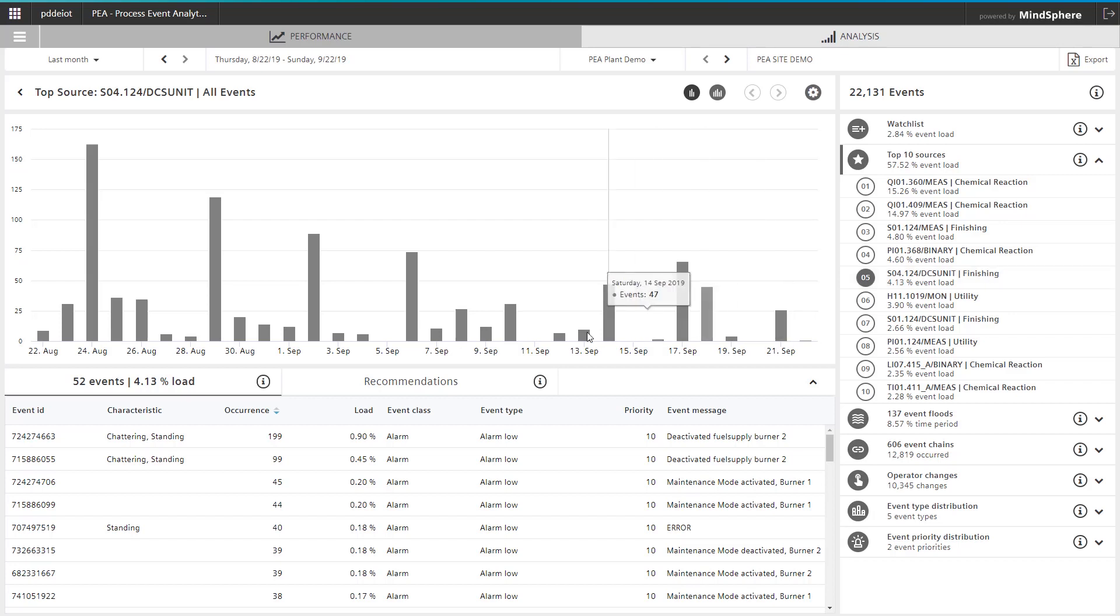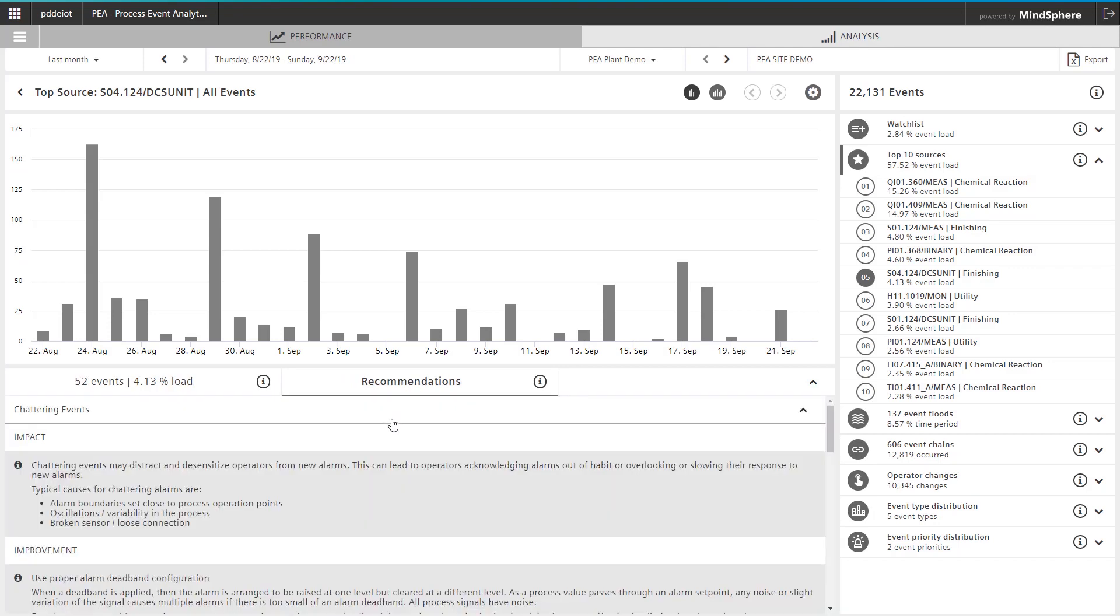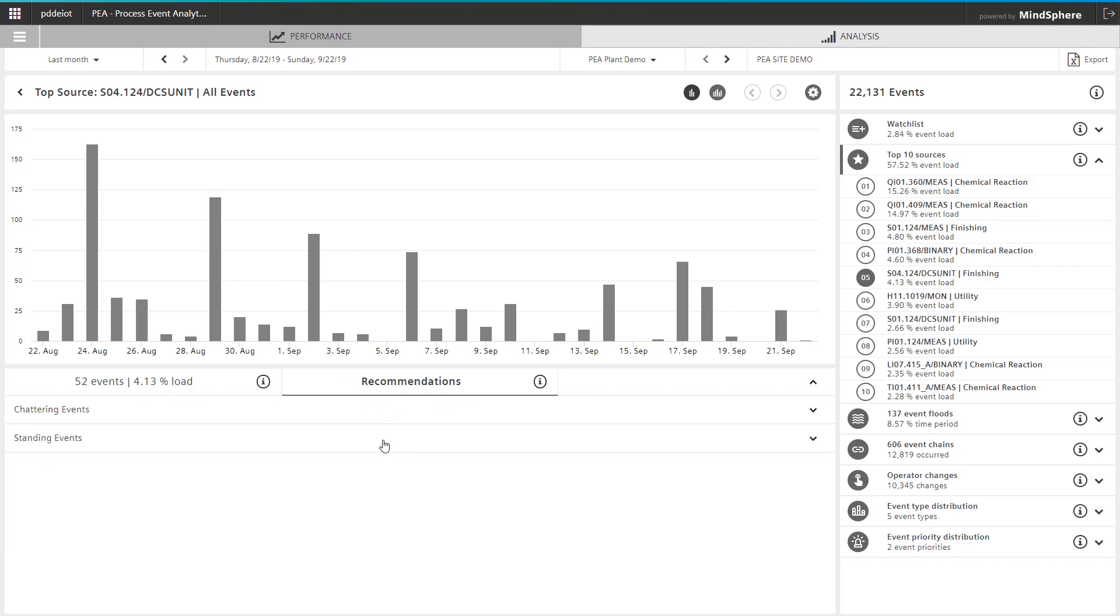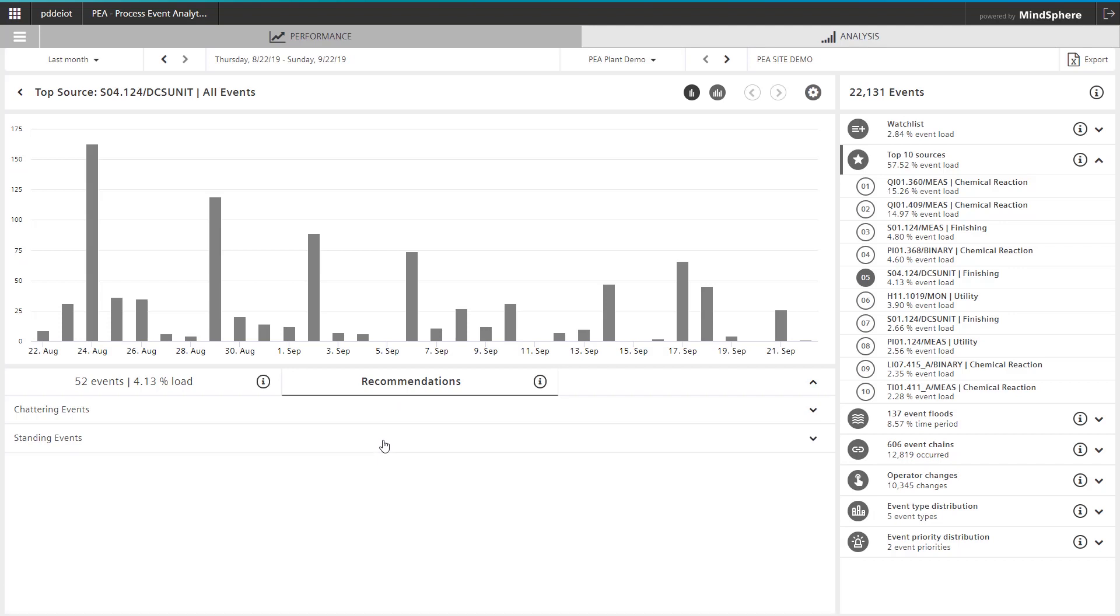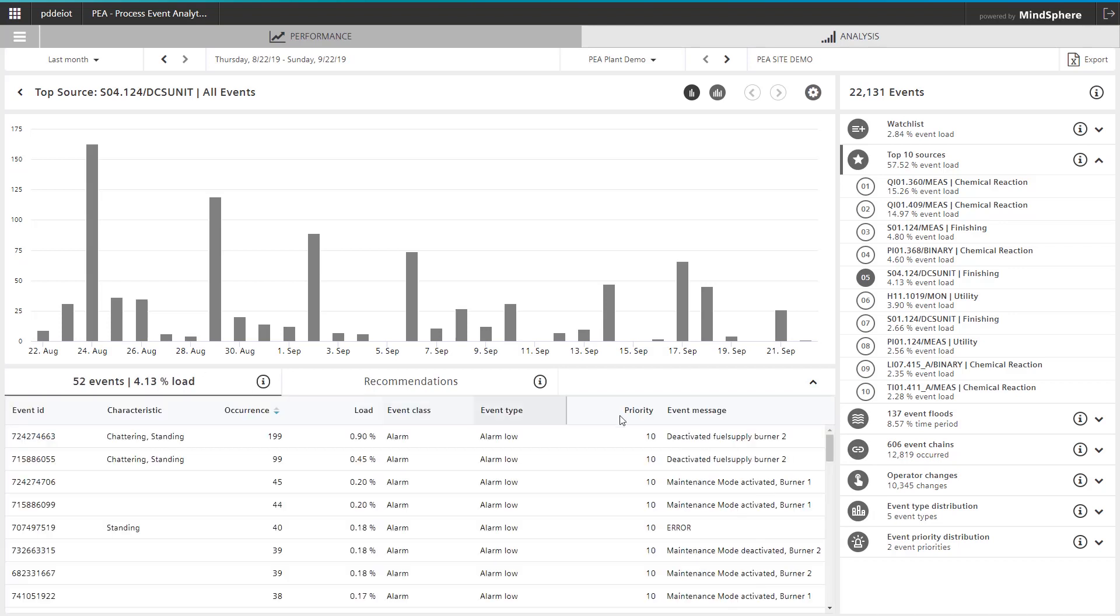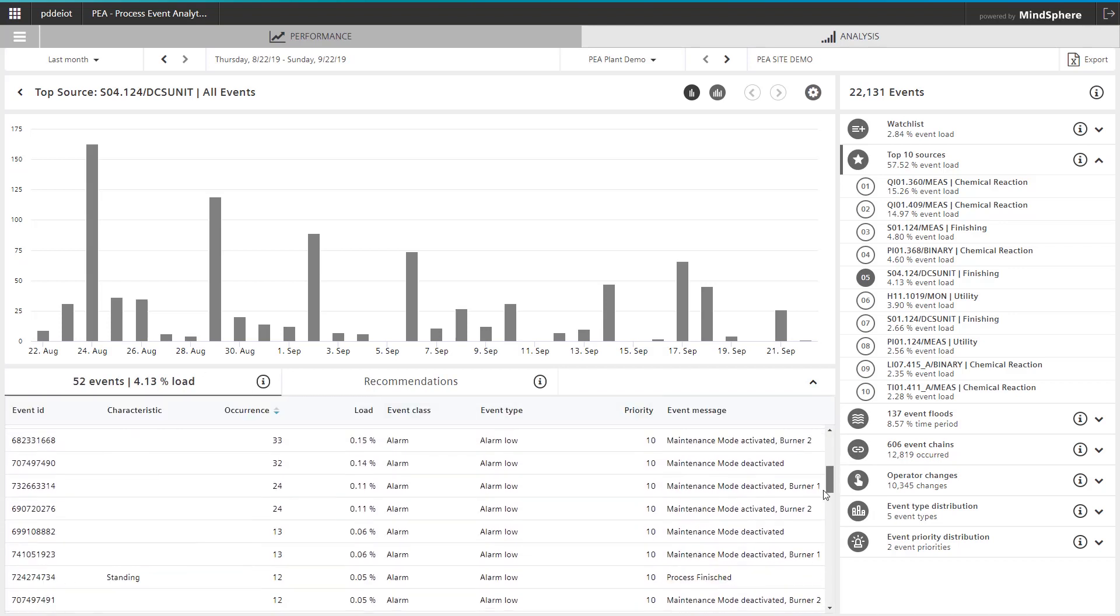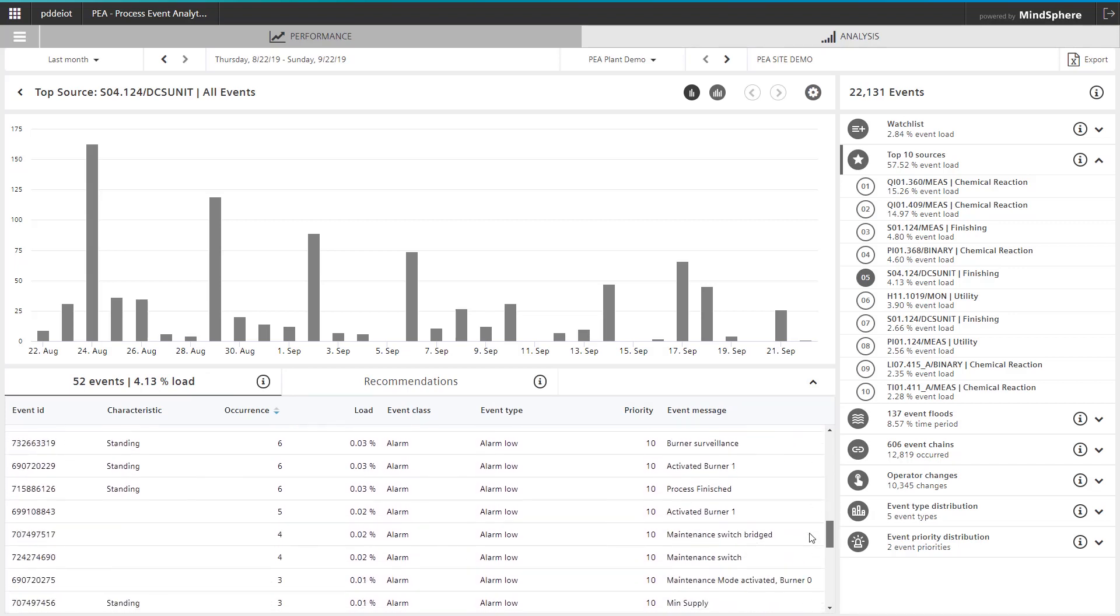In addition, the reporting behavior of an alarm is characterized and a recommendation for mitigation is given. In this concrete example, the messages would have accumulated at the end of the hit list and probably not been noticed. With the results of this analysis, you can check the operating philosophy of the equipment and reduce the workload of the operating personnel by optimizing it.